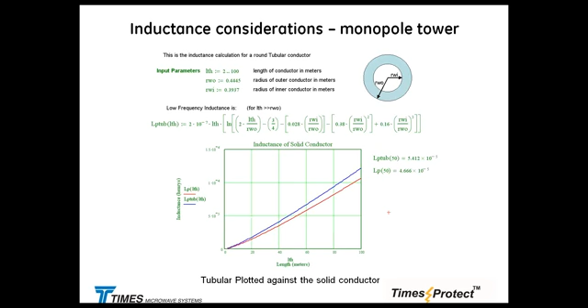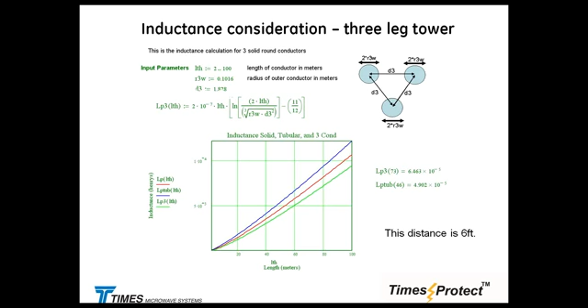Here is another example of calculating inductance for the three-leg tower, where we are talking about the distance d3. The larger the distance d3 between the tower legs at the bottom, the lower the mutual inductance. You can run these calculations based on 2 or 3 parallel conductors. Now a graphic representation of what will happen with a total mast inductance of 40 microhenries and a relatively small 18 kiloampere peak strike with a 2 microsecond rise time. The inductive voltage drop is calculated at 360 kilovolts peak.